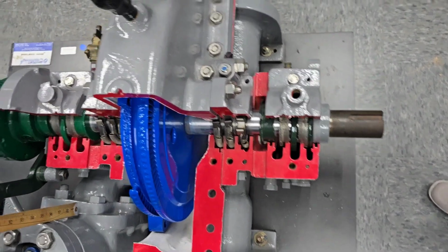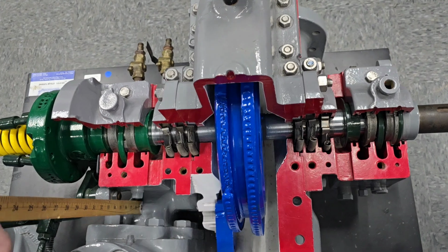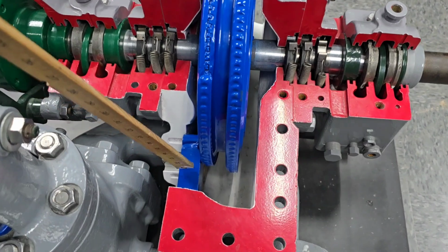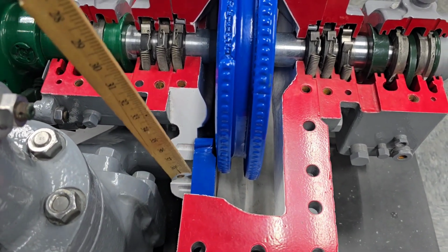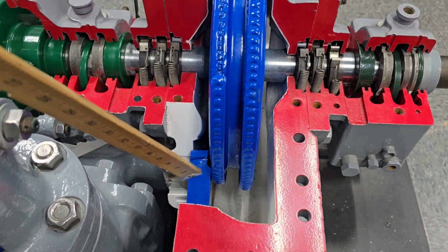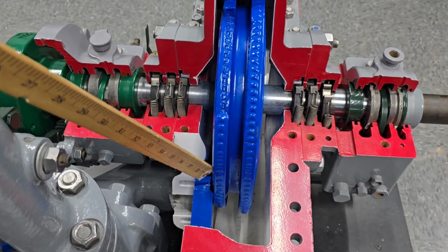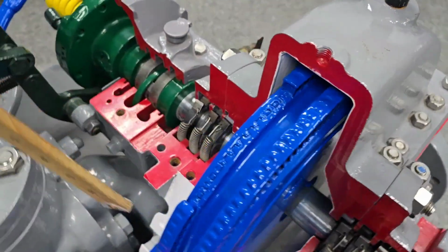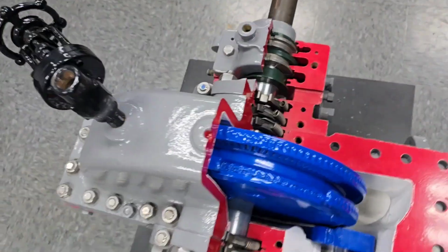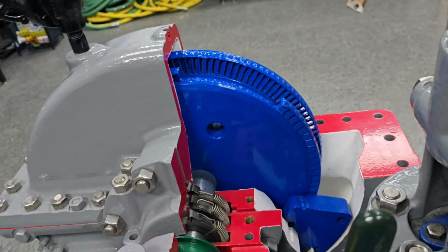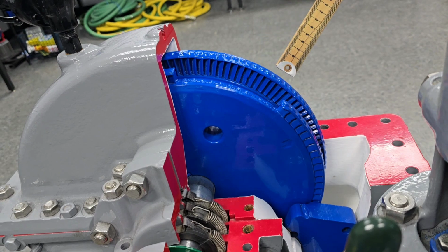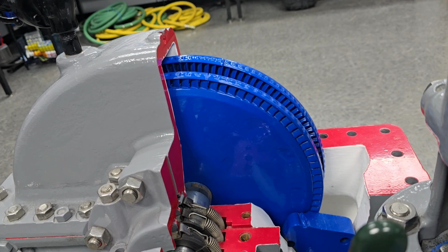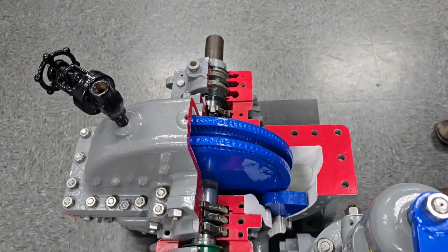The steam entering through the trip and throttle goes into a steam chest. The steam chest is directing the flow of steam to a nozzle block. The nozzle block, indicated right here, is going around the turbine. The nozzles are directing your steam towards your chevrons and buckets, which the steam is allowed to pass through. And this is where the transfer of energy from potential and kinetic to mechanical happens. So the nozzles direct the steam to the buckets, rotating the shaft that is connected to a piece of equipment.